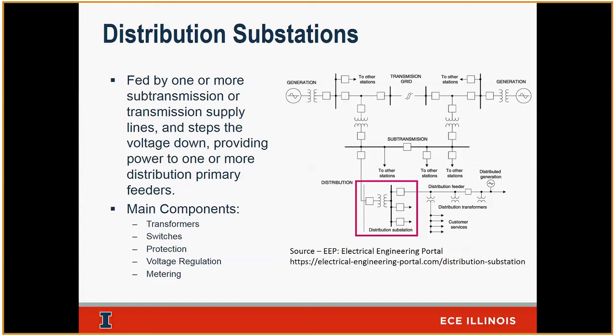From an analysis perspective, it doesn't really make a big difference. But that's what you typically have on the load side of the transformer. So we call them the high side and low side. That's the terminology we use for a given transformer. Transformers are defined by their capacity, and that's typically on an MVA basis. It's very common to see a 10 MVA or a 22 MVA in the Ameren world. And we'll show some examples of what these look like.